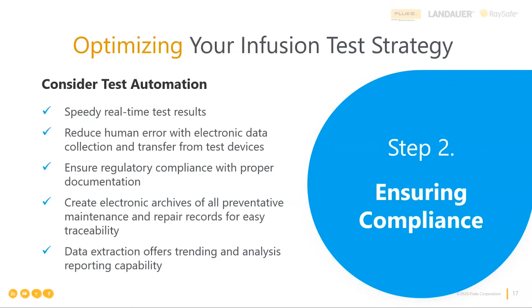And so efficiency produces productivity, helps you with compliance, and now your whole medical device quality assurance program really helps you. And by collecting the actual measurements against the pass-fail criteria, we begin to have a long-term trend that we can look at and set something called trend limits that help us identify failure rates. And from failure rates, we can begin to predict what is going to happen, and then have the right parts at the right time to be able to do scheduled repairs. That reduces the amount of stuff that just shows up at the biomed shop door and says broken, right? It can help reduce all of that. When you really run a system well, that's what you get.